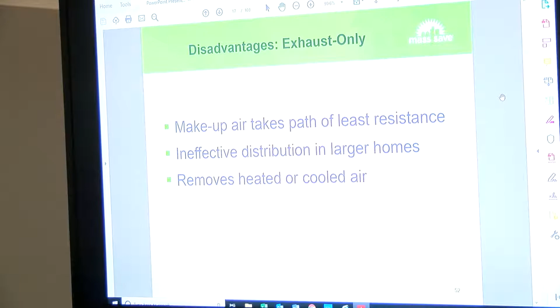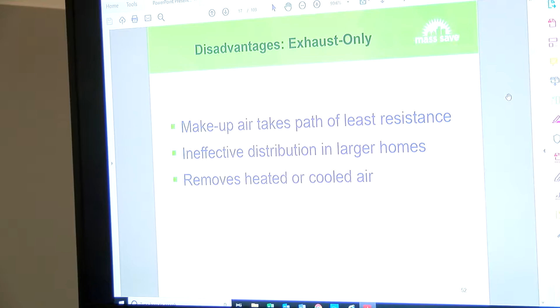Yep. So the disadvantage of an exhaust-only system, again, is that it creates a negative pressure within the house. The makeup air takes the path of least resistance. We try to have it come through the windows, but it's still coming through the basement and the crawl spaces, if they're not sealed correctly. Yes. And I've heard horror stories of too much negative pressure causing problems with combustion appliances and gas appliances.